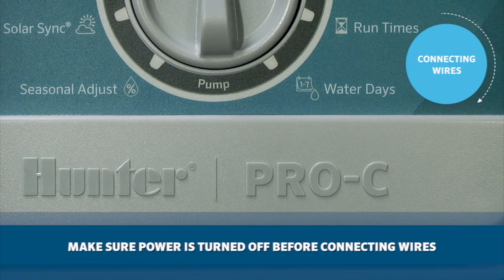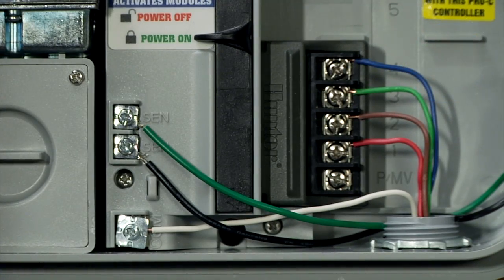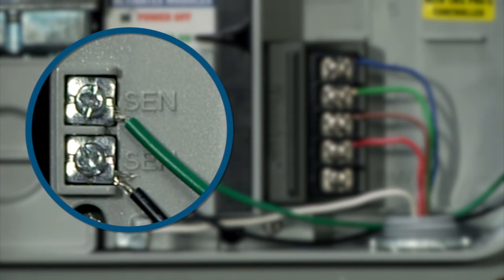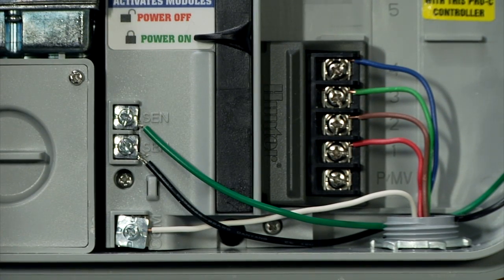Before attempting to connect anything to the controller, be sure to verify that the power is turned off. Connect the green and the black wires coming from the sensor — or from the sensor receiver in the case of a wireless sensor — to the two sensor terminals marked SEN on the controller, making sure to remove the metal jumper. The order of the wires does not matter.